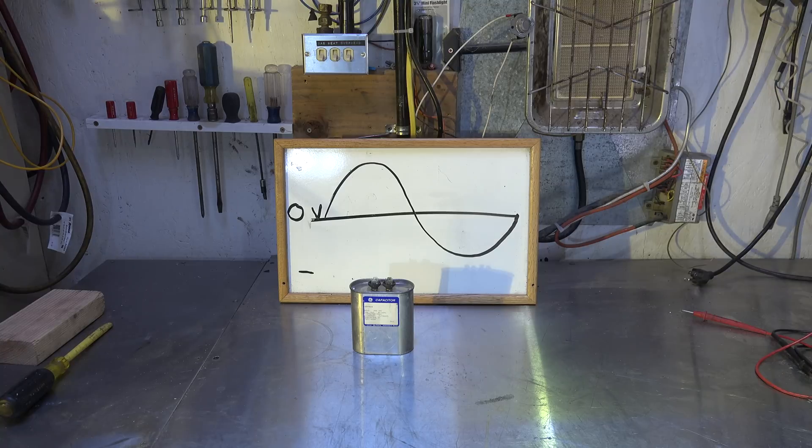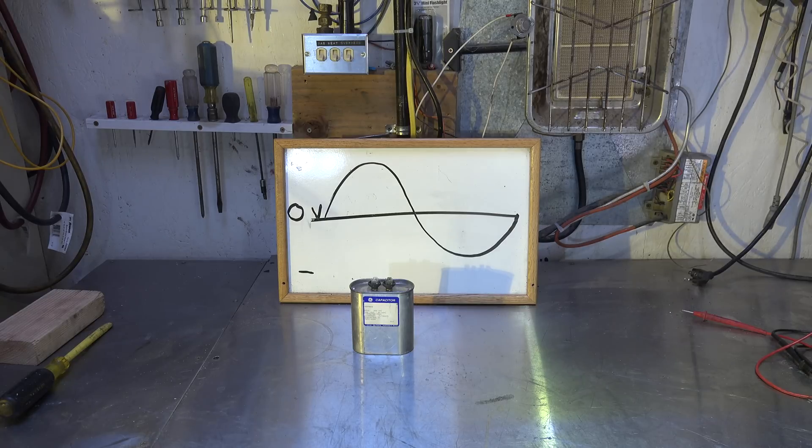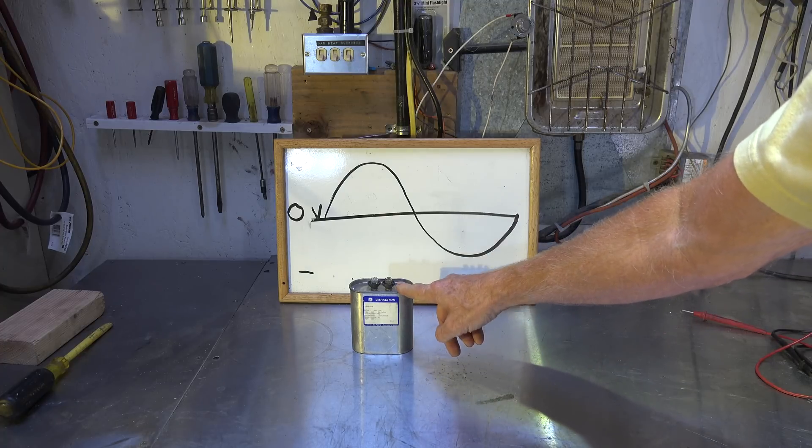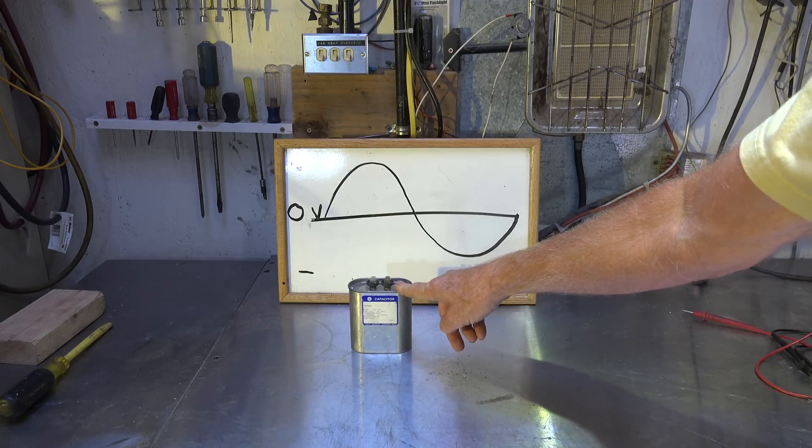Now I did a video on a PSC motor where I removed the capacitor and just put power straight to the run winding. Motor starts fine, but it overdraws - it draws too much power because there's too much power going to the start winding. That capacitor is what is limiting the amount of power that's going to the start winding.